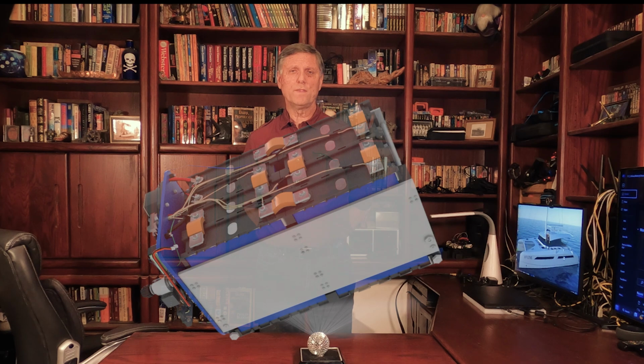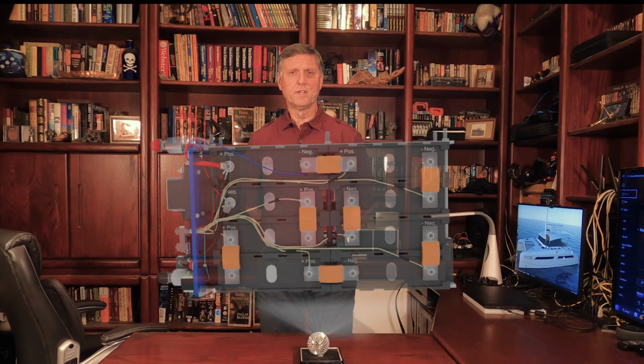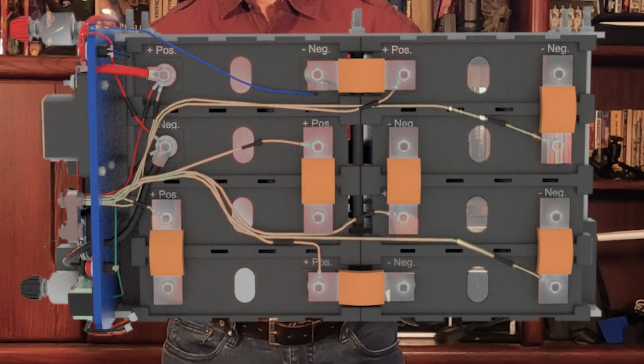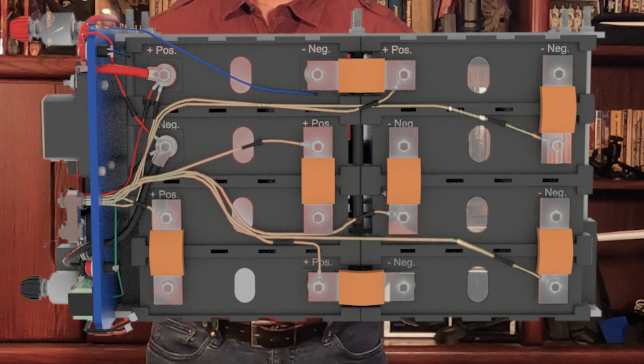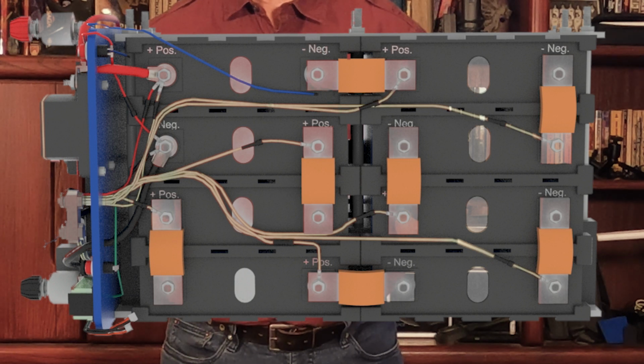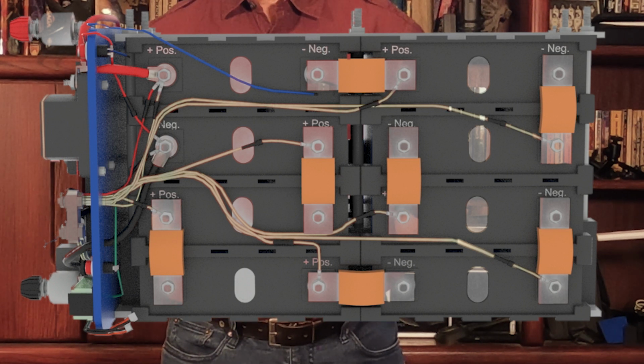Remember that we have these cells under compression using springs, which means that as the cells charge and discharge, they will expand and contract slightly. We don't want that movement harming the cell terminals due to hard bus bars, so we're using flexible bus bars, which allow expansion and contraction. Those are the orange bars you see now. While we're here, you can also see the individually fused BMS wires, which, among other things, are used to balance the cells.